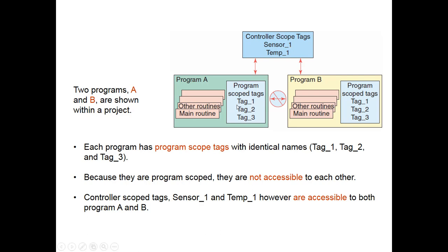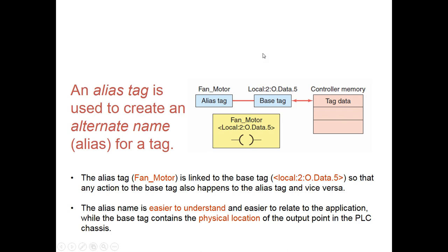Be aware that local tags cannot be shared with subroutines or the main. An alias tag is when you're creating a name for the IO — you come up with a tag name like 'fan motor' and give fan motor an address. Fan motor is the alias for the address. It's backwards from SLC 500s where you take the address and give it a name; here you have a name and give it an address. It's easy to remember 'fan motor' instead of, say, the second slot output on the fifth bit.